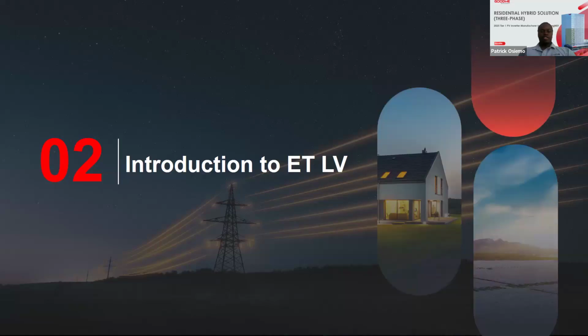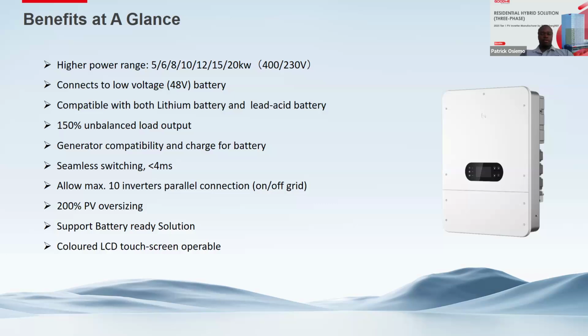Now, with that noted, I'd like to introduce you to the main topic that we'll be discussing today, which is a three-phase residential hybrid inverter brand called the ETLV. And these are the benefits that you'll be getting from the ETLV. So what are the power ranges of the ETLV? We have the smallest, which is the 5 kilowatt, and they are packaged up to the 20 kilowatt. So 5, 6, 8, 12, 15, and 20 kilowatt. These are three-phase. So we have the 400 volts line to line, and for line to neutral, we have the 230. It's a low voltage inverter.